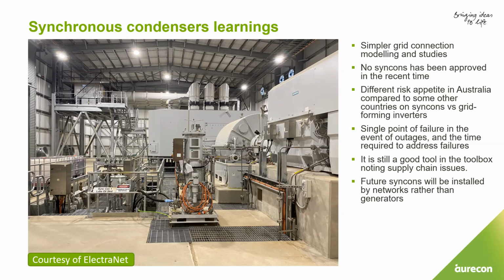We might think these are highly reliable equipment. I'm not saying they're unreliable, but we've had multiple failure events, and essentially a single point of failure: if a synchronous condenser of say 200 megawatts is gone, game over, and it takes many months to fix. Despite that, I think it's still a good tool in the toolbox, especially with the supply chain issues we're seeing—we're all competing in Australia, Europe and the US for a share of this very limited and scarce supply chain, especially with lithium ion batteries. So I'm not ruling out synchronous condensers by any means, but we're not seeing much of it happening.